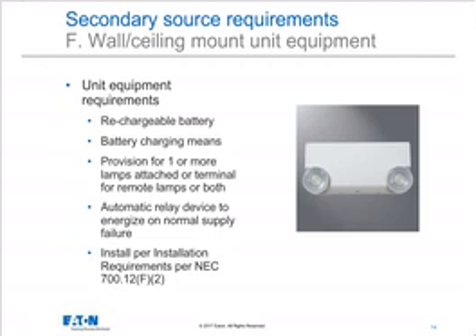But each one of these devices has to be tested every month to make sure that the lights work, that the battery is good, and the battery charger works. And if I have 200 or 300 of these in a medium-sized office building, maybe a 4-story building, for example, then that's going to take a small crew of people half a day to do that, and it has to be done every month. And the cost of that can be surprising.